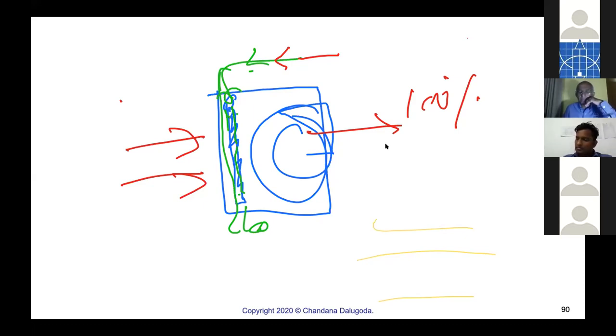One thing I want to raise is that the exemptions given in 90.1 are exemptions, not limitations. Why have they given us exemptions for the CAV? What I understood was that when you go for high delta T cooling coil selections, you have to go for a deeper coil to achieve the same off coil conditions. Then your air side pressure drop slightly increases. With a CAV, since your flow rate is constant, you are wasting slightly more pumping energy because your air side delta P is higher than in a conventional design. That is why I see they have given it as an exemption. It is not a limitation.